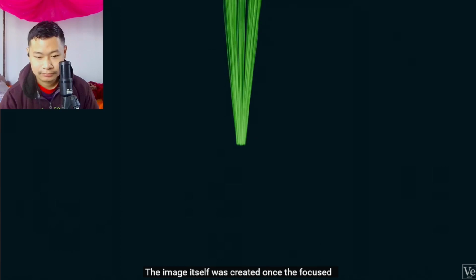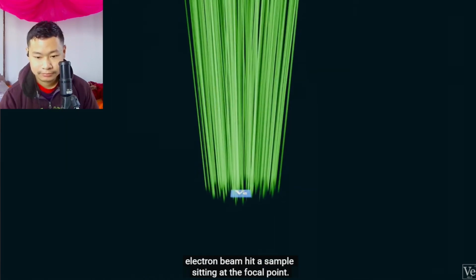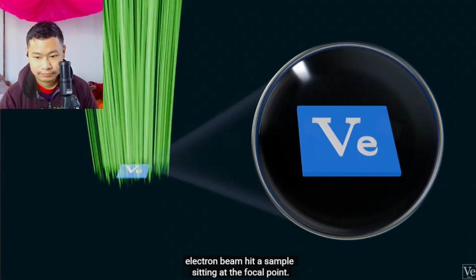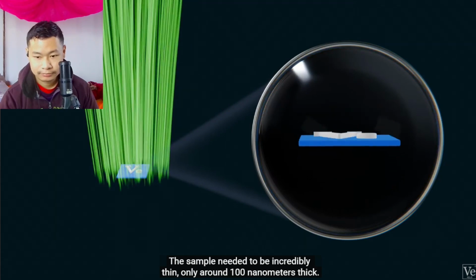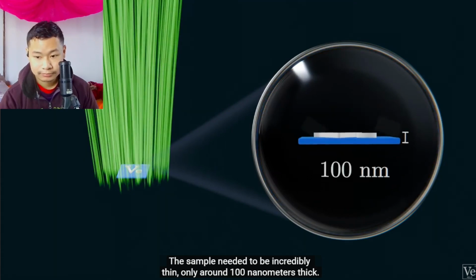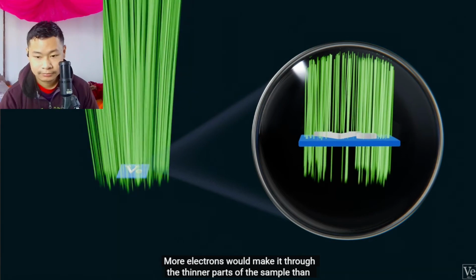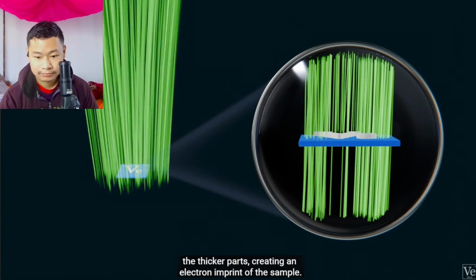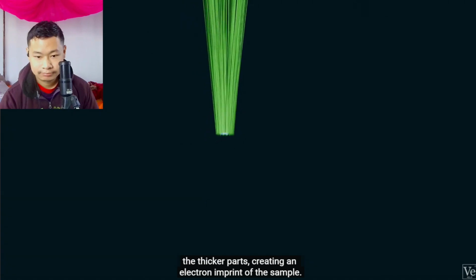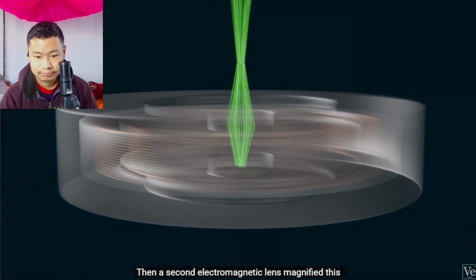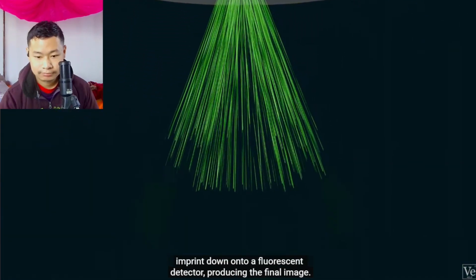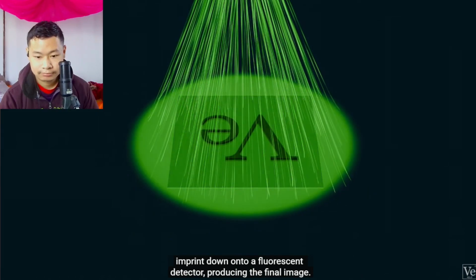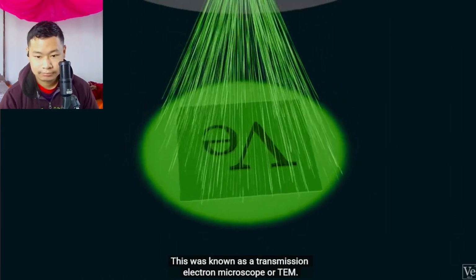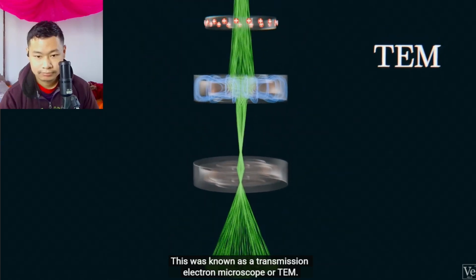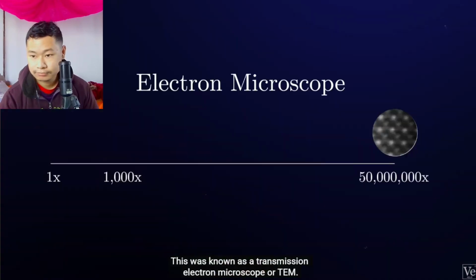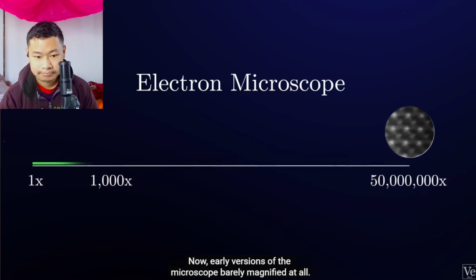The image itself was created once the focused electron beam hit a sample sitting at the focal point. The sample needed to be incredibly thin, only around 100 nanometers thick. More electrons would make it through the thinner parts of the sample than the thicker parts, creating an electron imprint of the sample. Then a second electromagnetic lens magnified this imprint down onto a fluorescent detector, producing the final image. This was known as a transmission electron microscope, or TEM. Now, early versions of the microscope barely magnified at all.